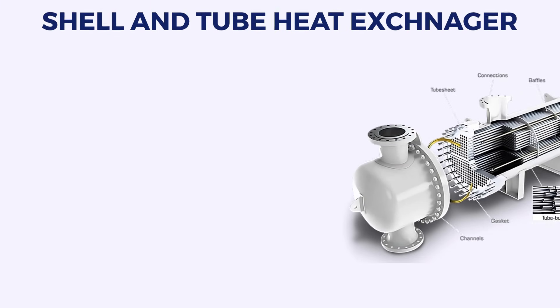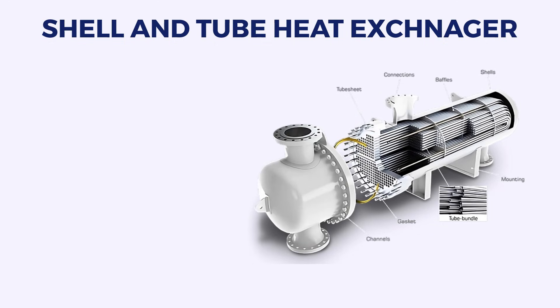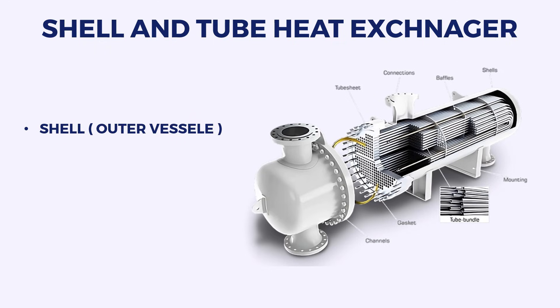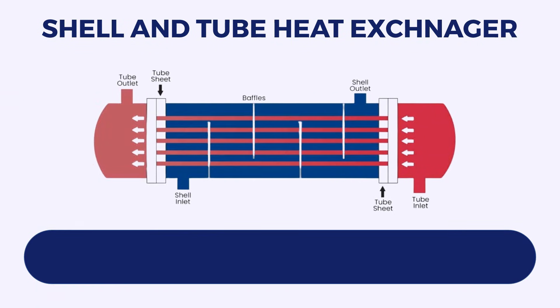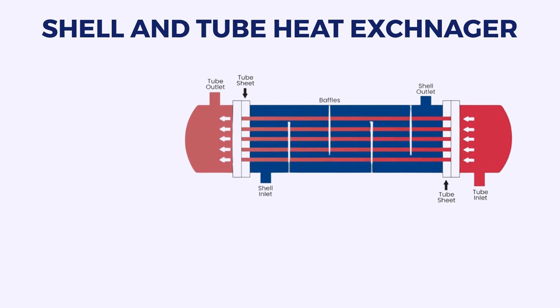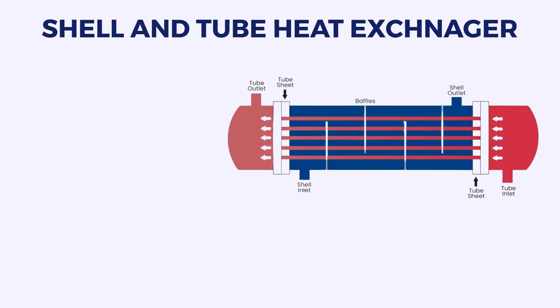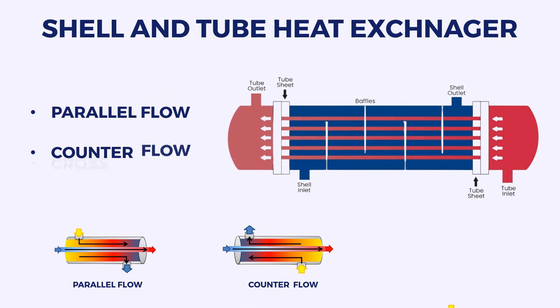Shell and Tube Heat Exchanger. A shell and tube heat exchanger is a type of heat exchanger that consists of a shell (outer vessel) and tubes (inner vessels) through which fluids flow, facilitating efficient heat transfer. The fluid flowing through the tubes is known as the tube side, while the fluid outside the tubes is the shell side. Tube side and shell side can have different flow arrangements, including parallel flow, counterflow, and crossflow.